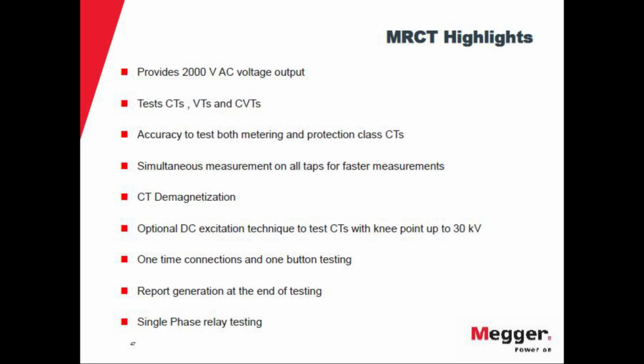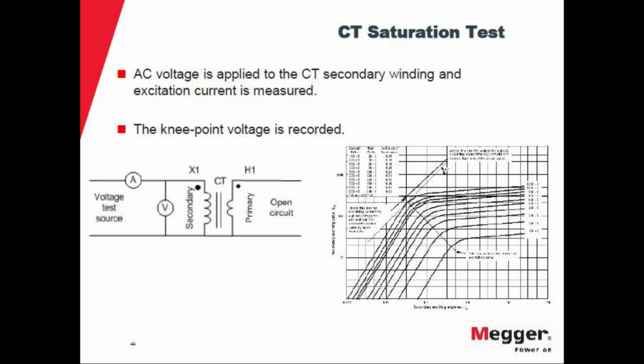As I was mentioning, the instrument can perform simultaneous measurements on all taps, so it performs a faster measurement. And it can perform demagnetization on CTs, with an AC signal or a DC signal, so it can work very well with both. Some CTs have a very high saturation point, so let's go a little bit into the detail of these. On this knee point, we can see that the saturation is happening around, well, in this case probably 400 volts. So you need just 400 volts to saturate this CT. But there are CTs that saturate at 30 kilovolts, and this only goes up to 2,000 volts.